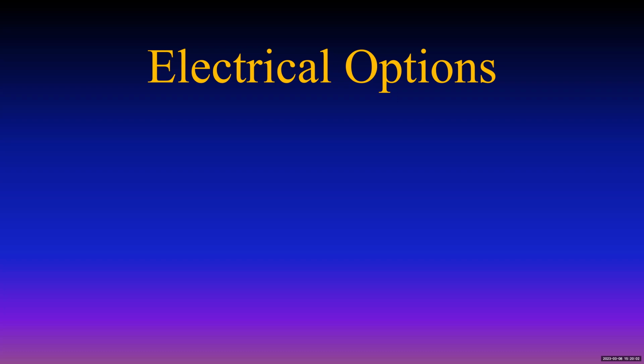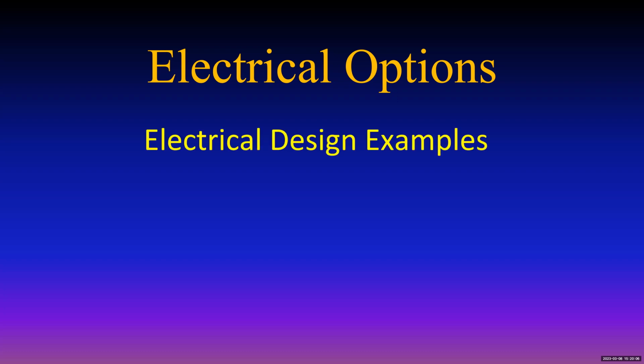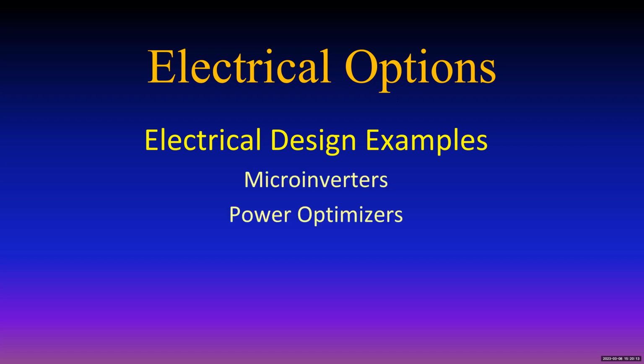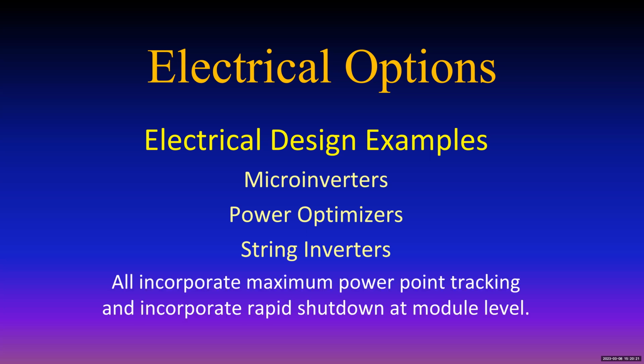All right, so what are the electrical options for this particular system? So let's do some example designs. We'll do one with microinverters, we'll do another one with power optimizers, and we'll do yet another one with string inverters, and compare the design procedure for these, okay? Now, every one of these inverters or optimizers, an optimizer is not an inverter, it's DC in and DC out, but it does have maximum power point tracking, so it knows exactly how much DC out that it needs, but it also wants to find the maximum amount of DC in. And all of the maximum power point tracking, they work on the DC output of the modules. Okay, so let's see what we can do here.